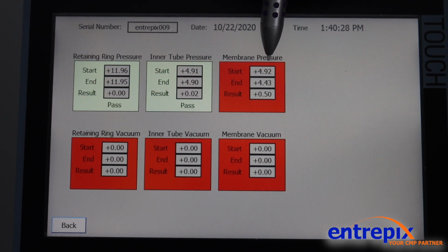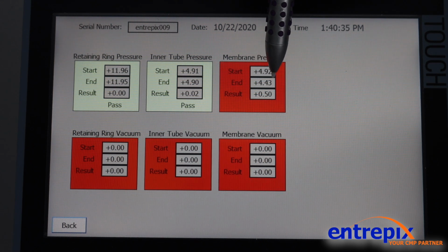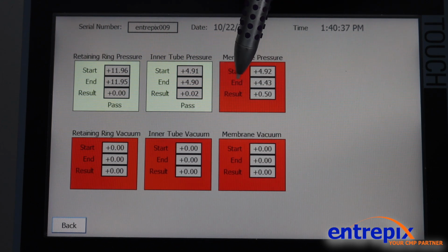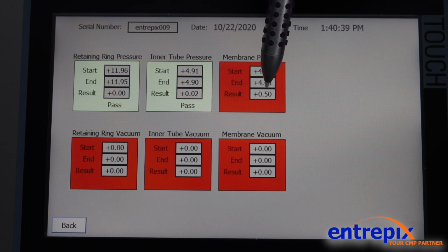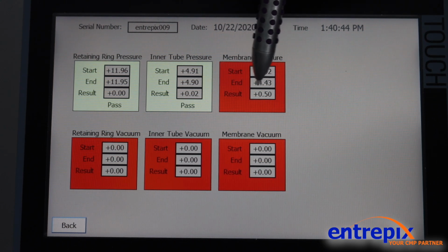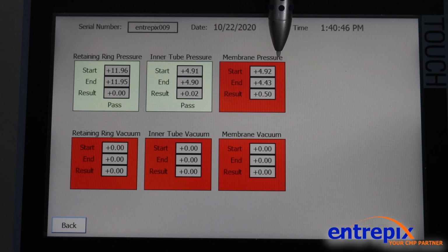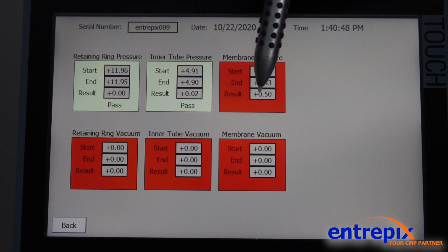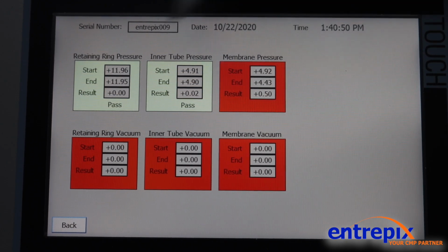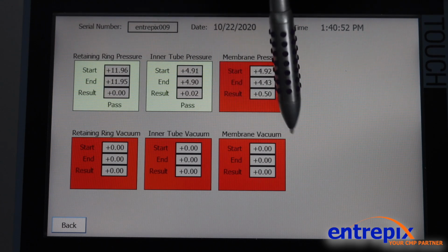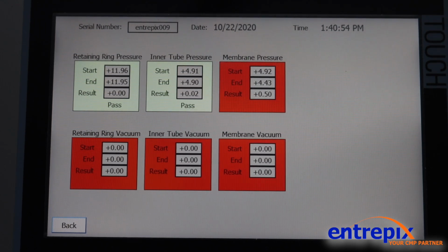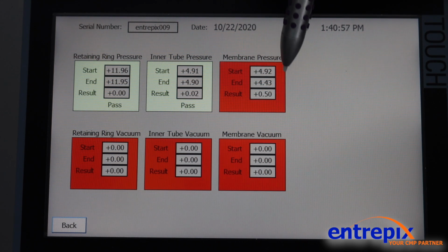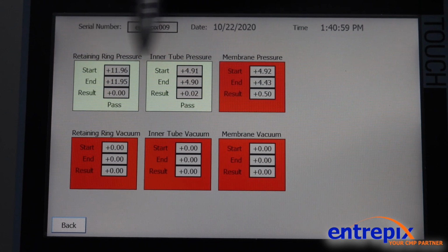So here it's showing that the beginning value for the pressure test was 4.92. The end pressure was 4.43, indicating a result of greater or 0.50, which is well beyond the 0.1 requirement for pressure. When it noticed this alarm, it aborts the process, so all of your other variables remain at 0. Now you would go into your manual screen and you could troubleshoot this section independently and look for crosstalk between the other zones.